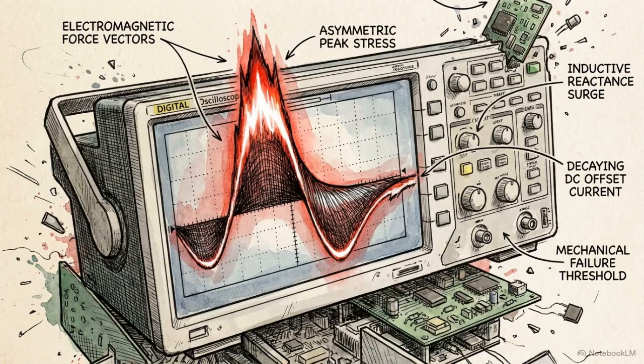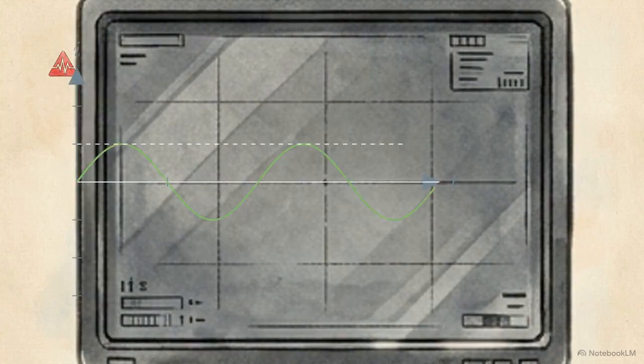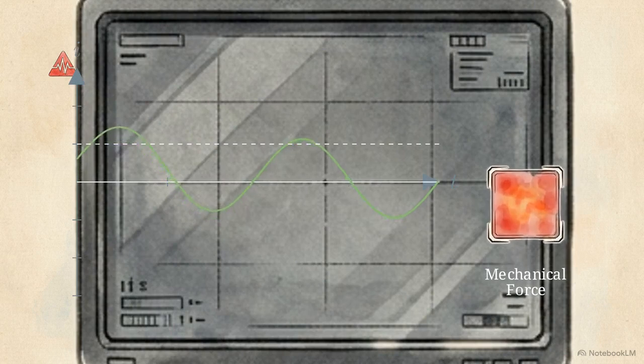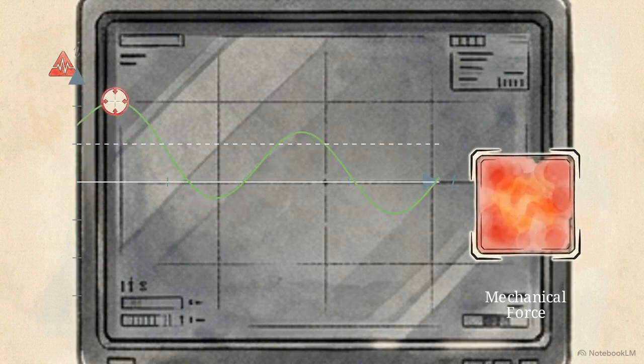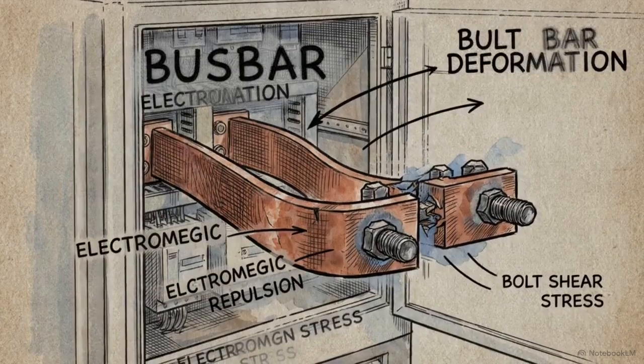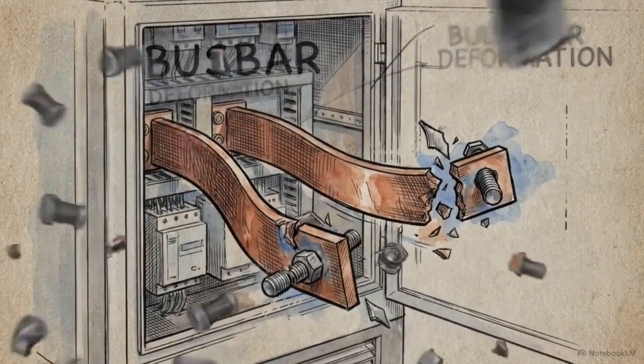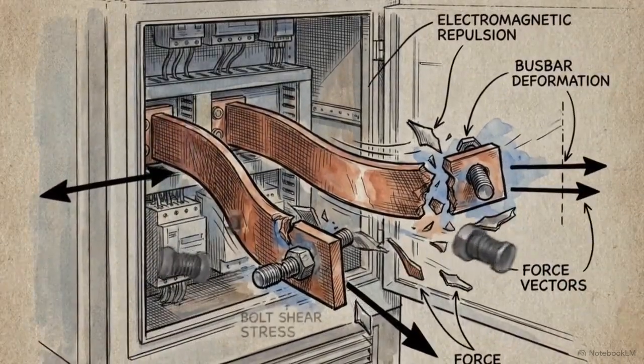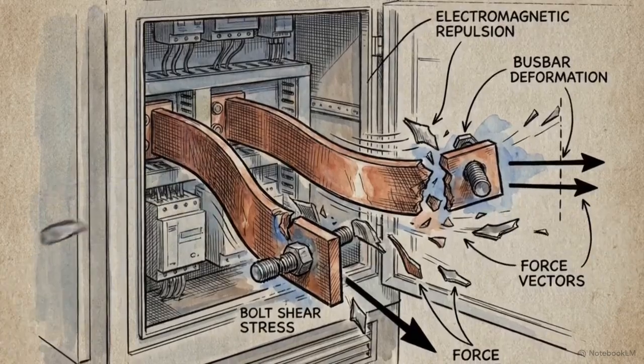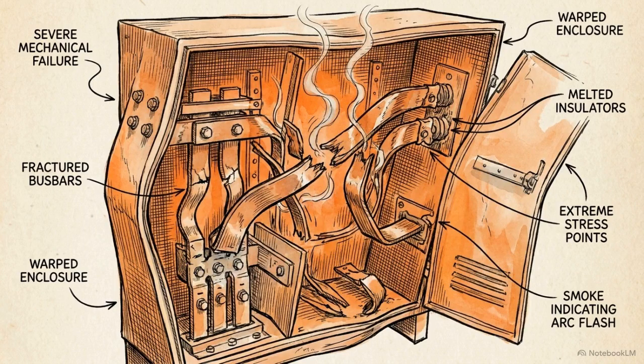massive, localized peak. The immediate danger hides in the first cycle of that shifted wave. The highest crest, the peak short-circuit current, reaches an impossible amplitude. Physical force scales with the square of the current. That artificially high peak acts as a mechanical bomb. The resulting magnetic fields exert thousands of pounds of shear force, instantly bending steel enclosures and ripping solid copper busbars off their physical mounts. If the equipment survives that initial concussive blow, a secondary threat takes over.